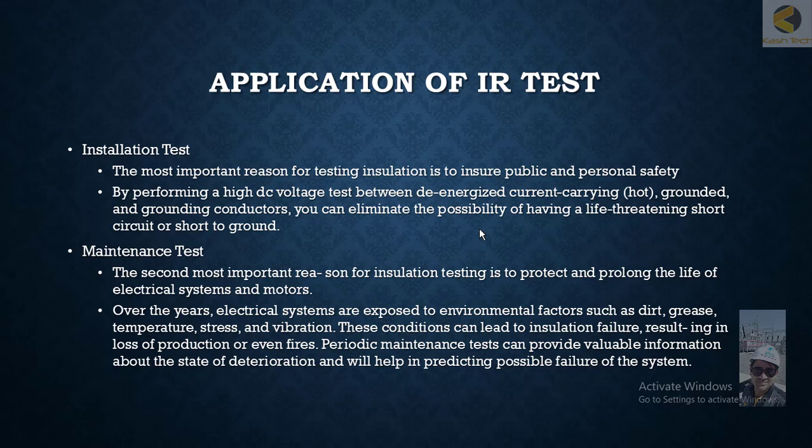The most important reason for insulation testing is to ensure public and personal safety. By performing a high DC voltage test between de-energized current-carrying and grounded conductors, you can eliminate the possibility of having a life-threatening short circuit or short to ground.